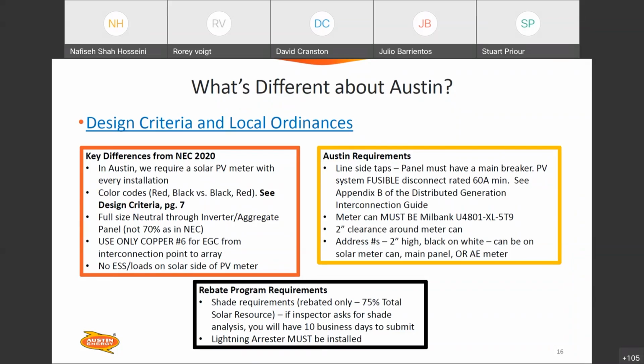Our meter can—this is the one and only one—is the U4801 XL5T9. That's the meter can you have to use. Pay close attention, because you could be forgiven for thinking another meter can with a 200 amp bypass handle and an AE stamp is approved, but it's not. Pay very close attention to the label inside the can—it's got to match.